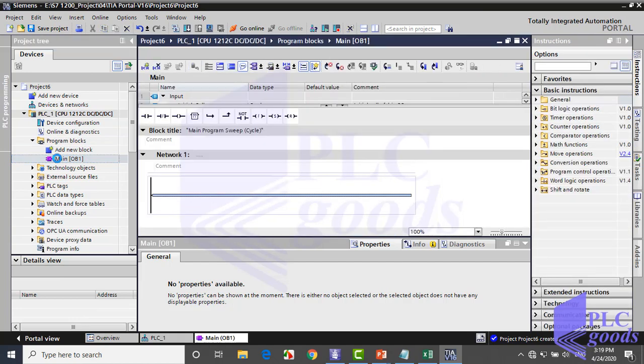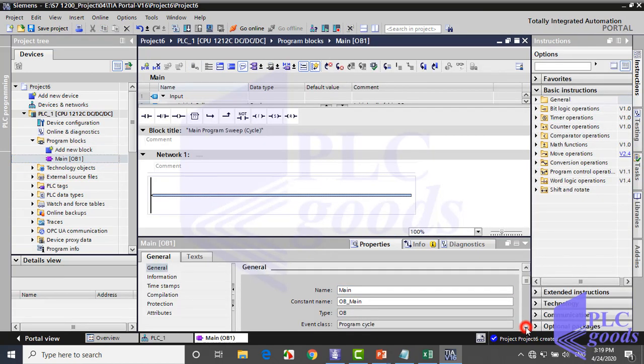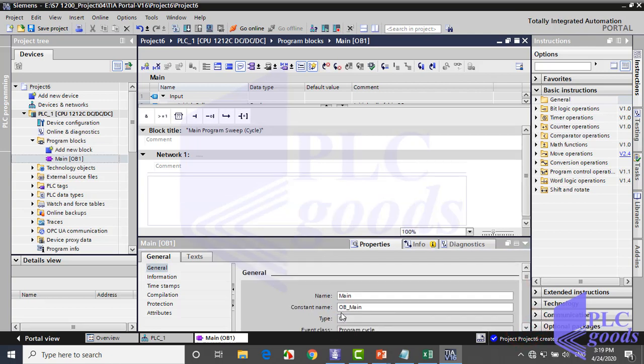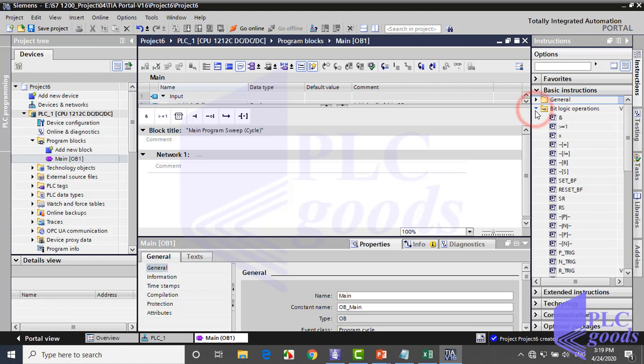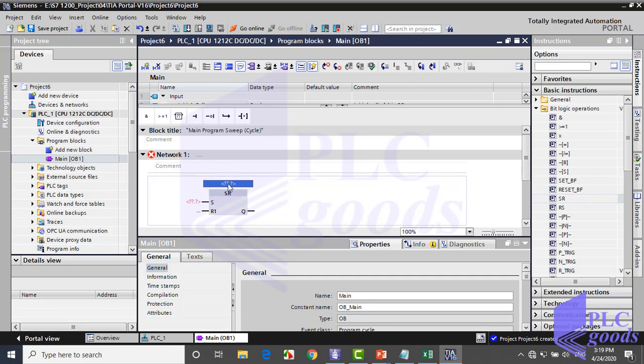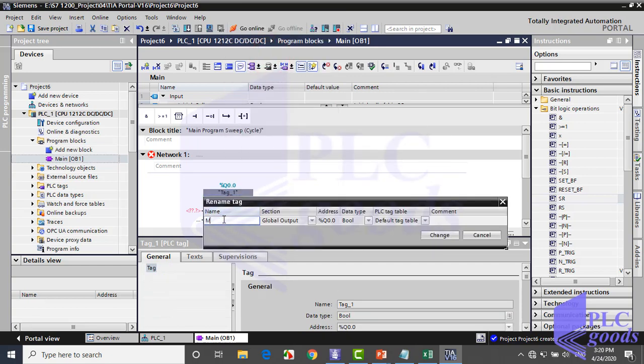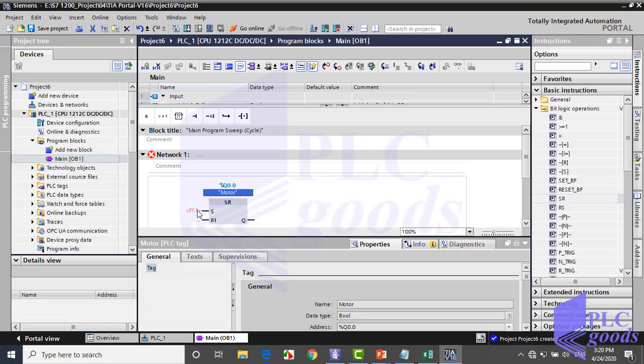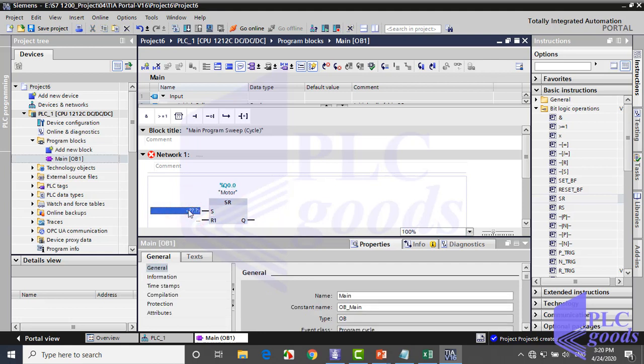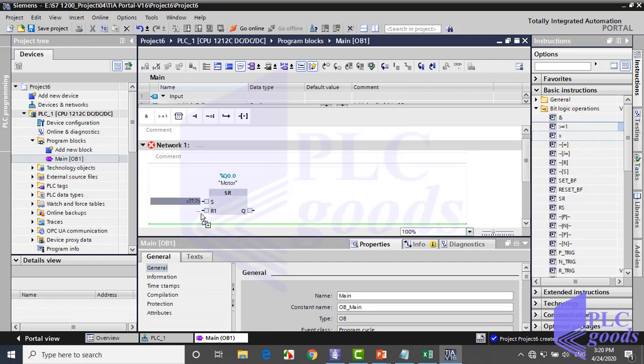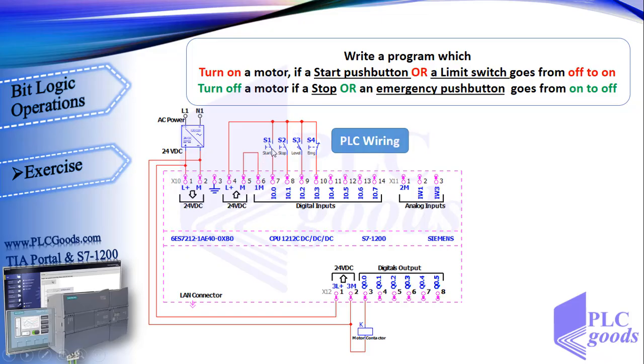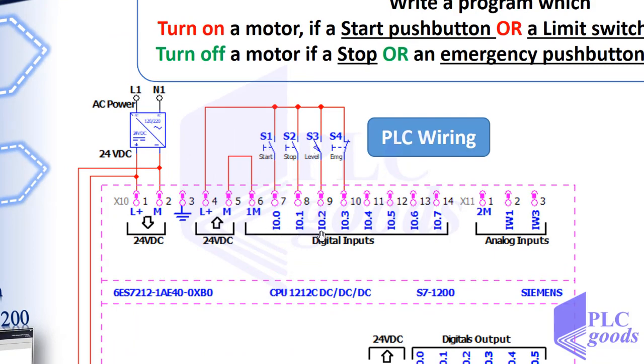Now let's write the program. Open OB1 block and use FBD language. First, I use an SR flip-flop to set and reset my output. We want to set the output with two push buttons using OR logic, so I insert an OR block. Looking at the PLC wiring, the start and level push buttons are connected to I0.0 and I0.2 addresses, so I define them at the OR block inputs.